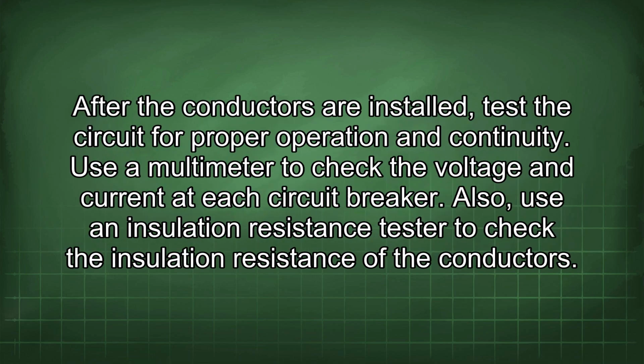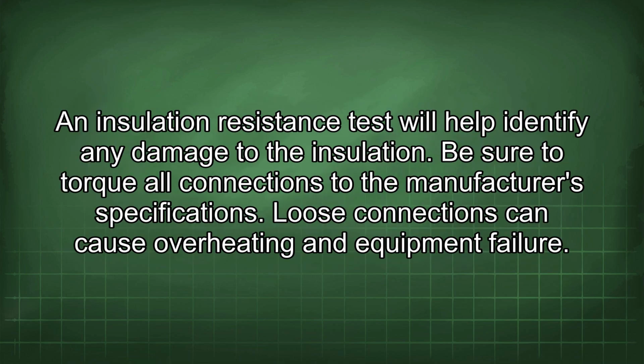After the conductors are installed, test the circuit for proper operation and continuity. Use a multimeter to check the voltage and current at each circuit breaker. Also, use an insulation resistance tester to check the insulation resistance of the conductors. An insulation resistance test will help identify any damage to the insulation.